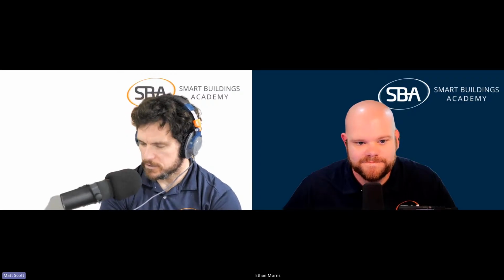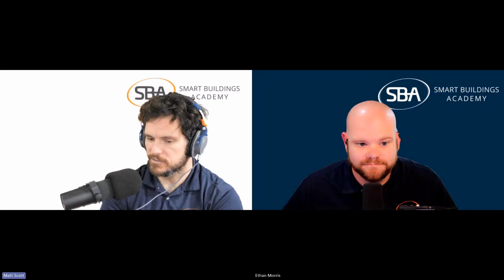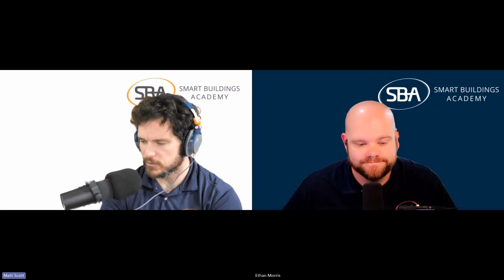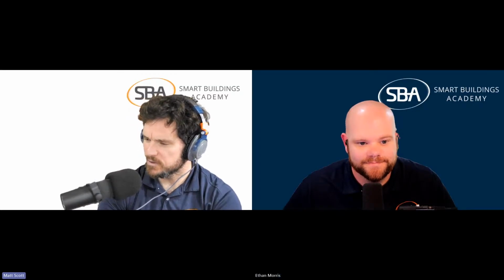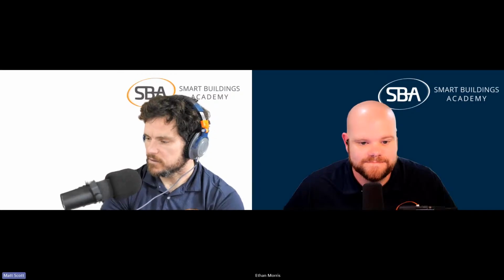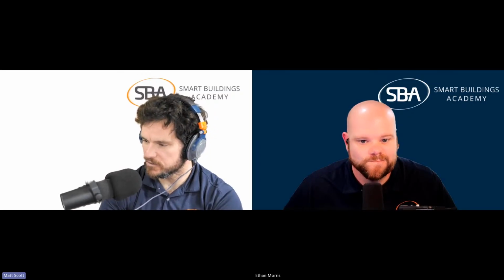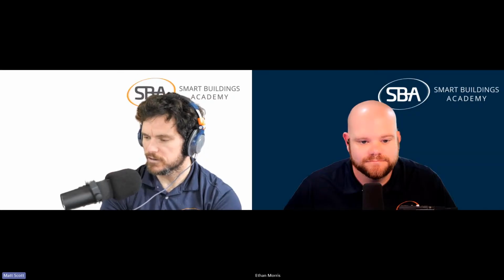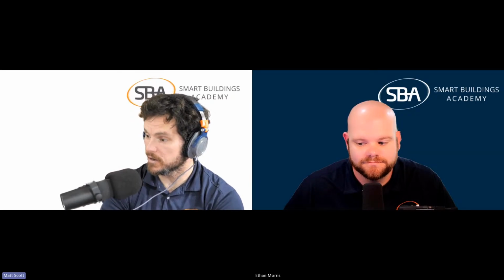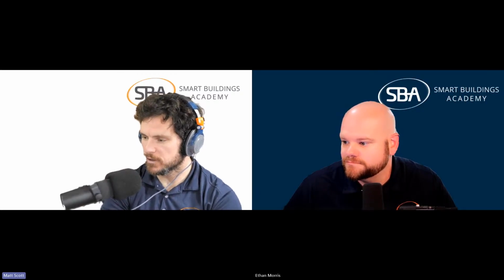Moving on, when would VRF not be a good fit? You mentioned one of the big reasons: large buildings or plants, centralized plants, that size of building, and the scalability just isn't there for VRFs. So anytime there's a large building, you probably won't see VRF, you'll see a chiller plant instead. Also, anytime there's a very cold climate, because of the vapor that comes along with the compressors, we don't want them to freeze up, so a very cold climate causes issues. Another thing these require is a decent amount of electrical infrastructure for the compressors, so there needs to be some electrical work, or the ability to house these from an electrical standpoint.